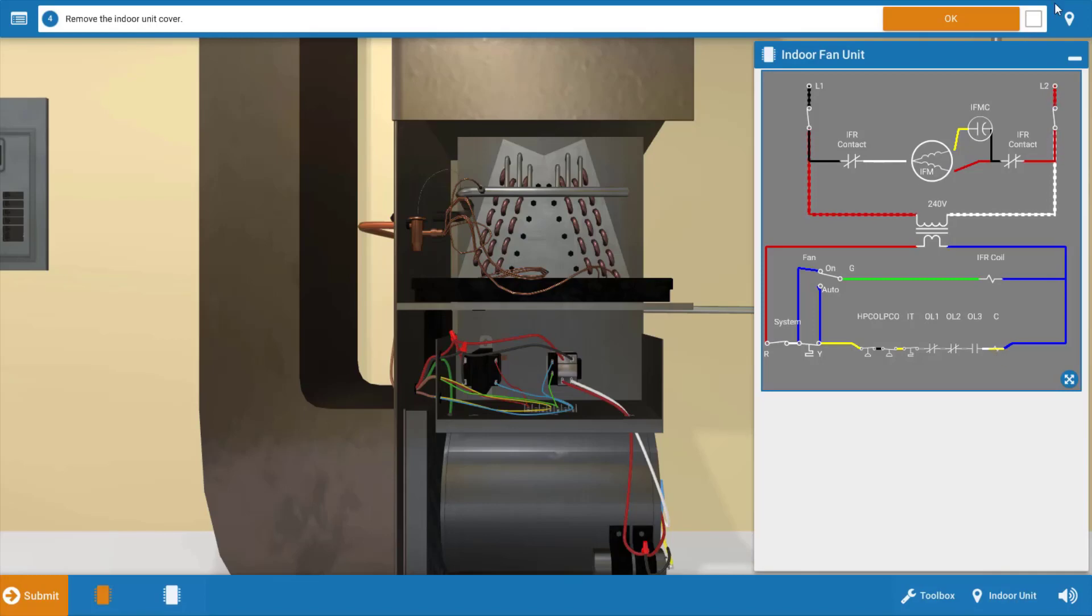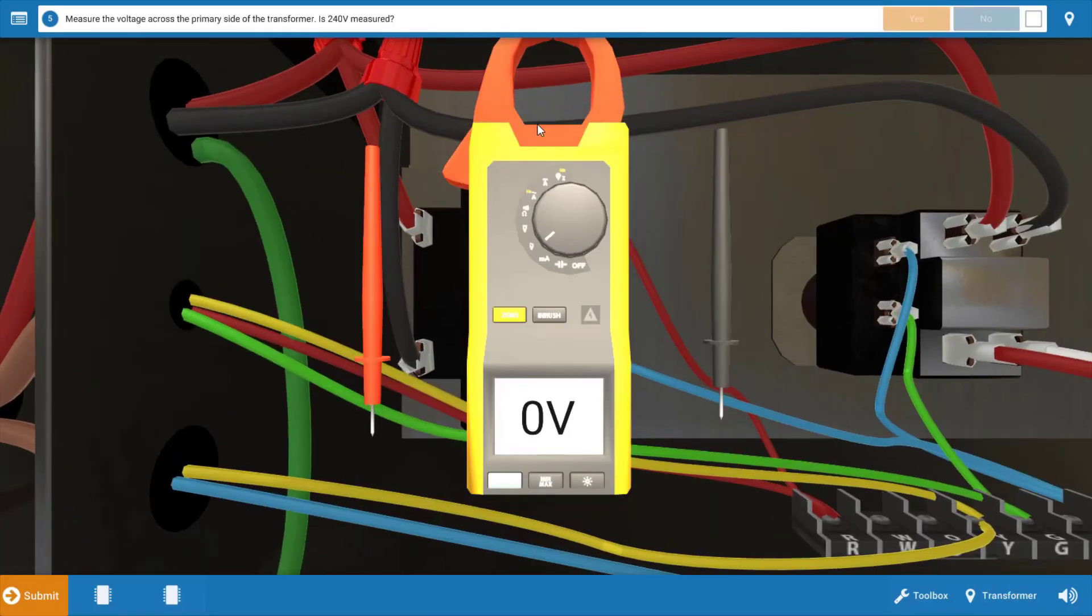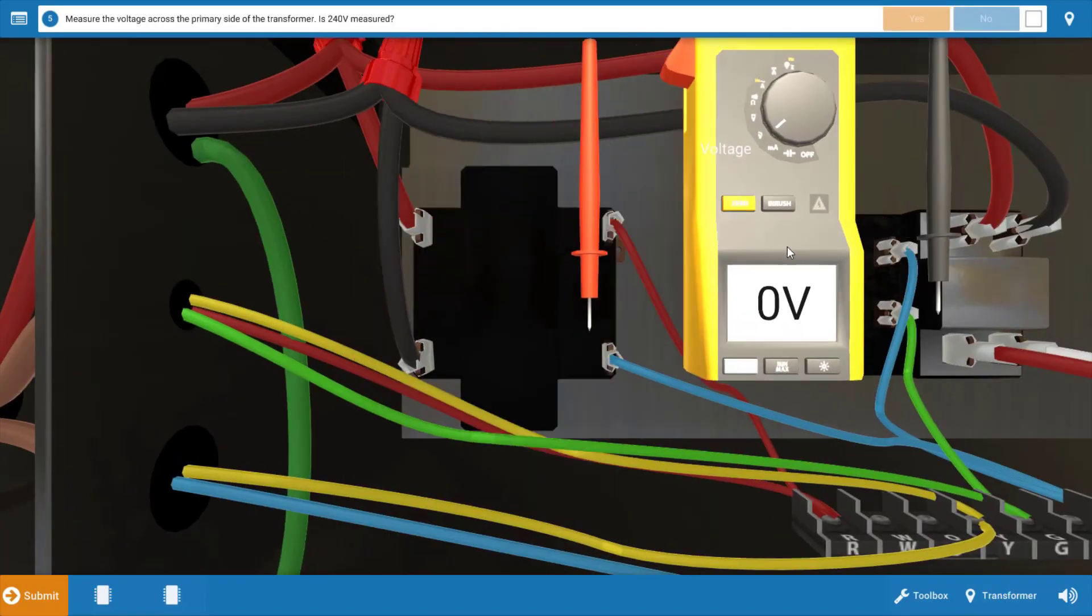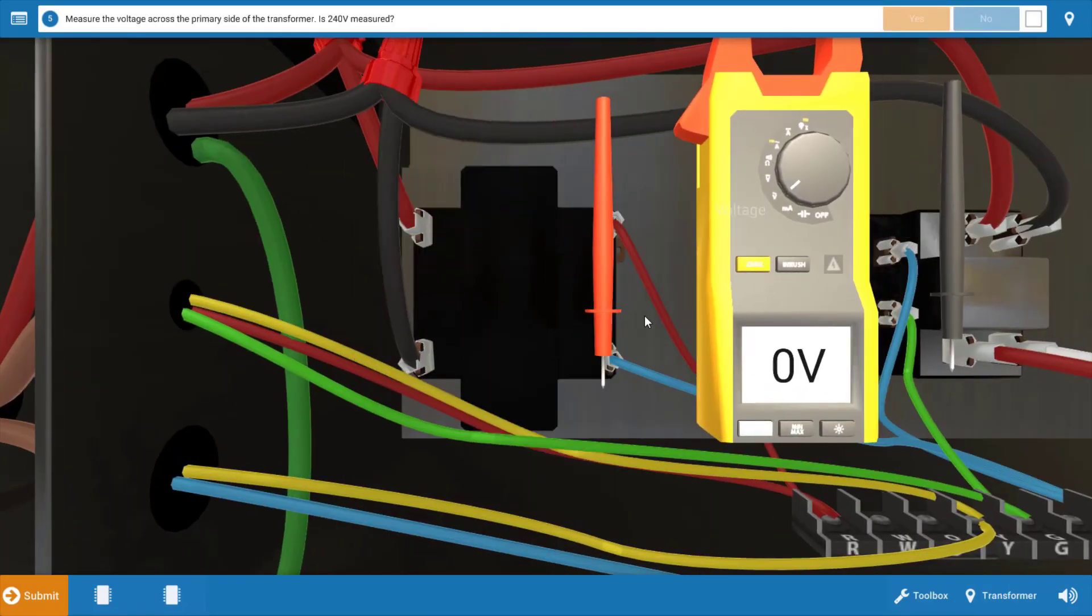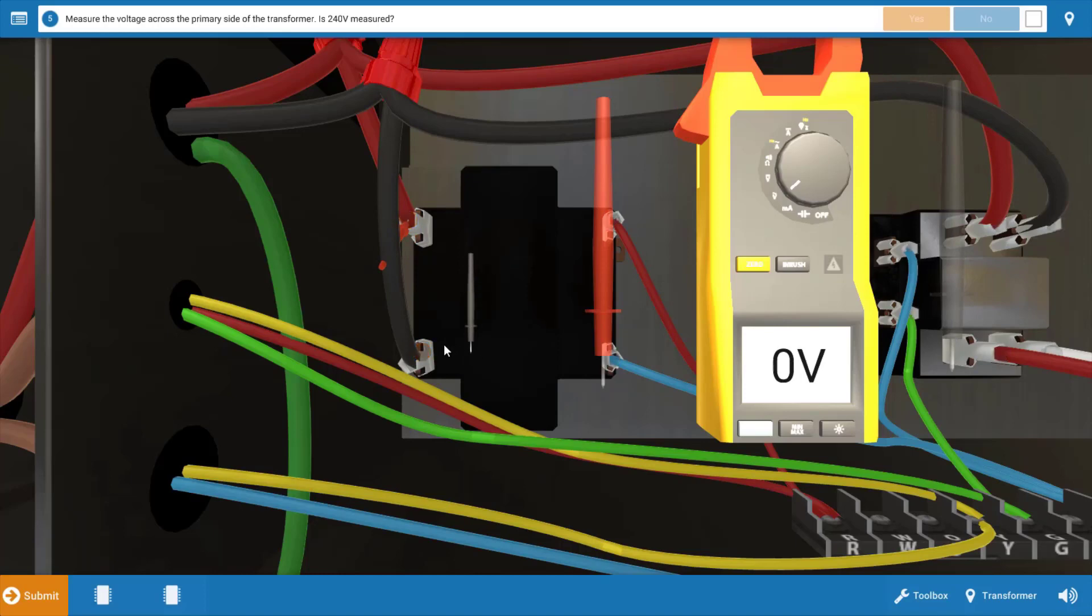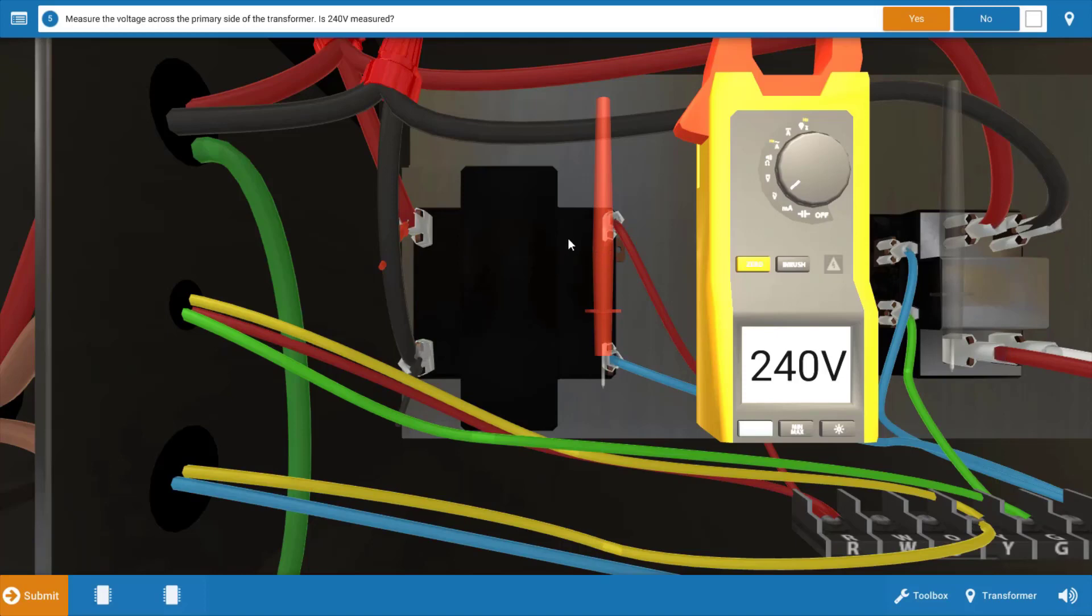So we've got three possible causes here, and now after clicking on the procedure guide that we've removed the cover, we're going to check for line power coming in, and this is 240 volts is what we're looking for here. So we're going to drop our meter leads at the primary connections of the transformer since this is a direct connection from the line voltage feed, and we have 240 volts, so that eliminates the main power as a possibility here.